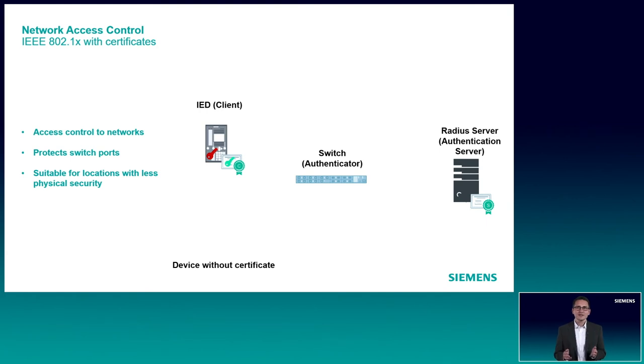In this example, we have the following setup. There is an IED that shall be allowed to connect to the network. It is connected in line mode to a switch. The switch is capable of forwarding 802.1X requests to a RADIUS server. The RADIUS server has the information which certificates are allowed to connect. A client certificate has been requested and installed on the IED. The simplified authentication process looks as follows.